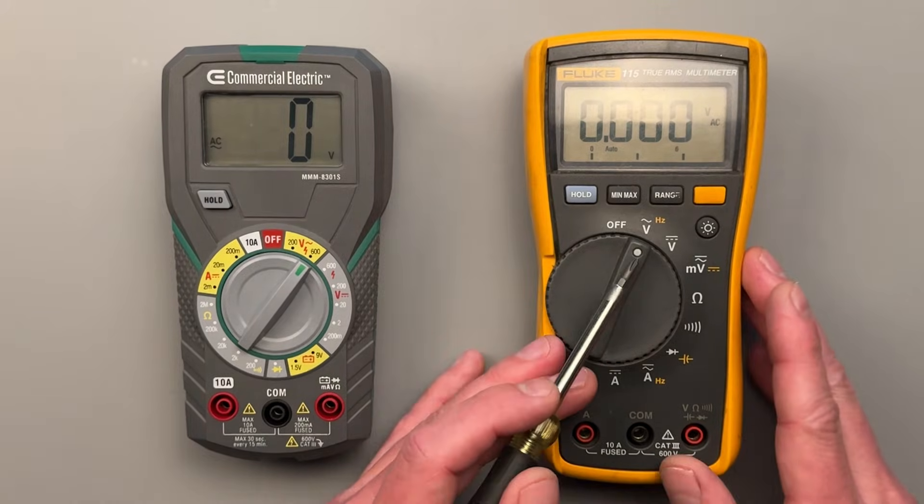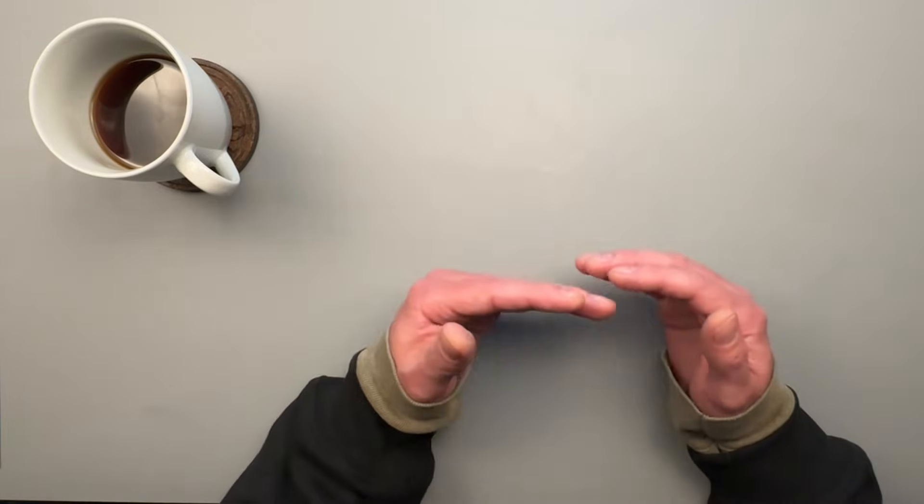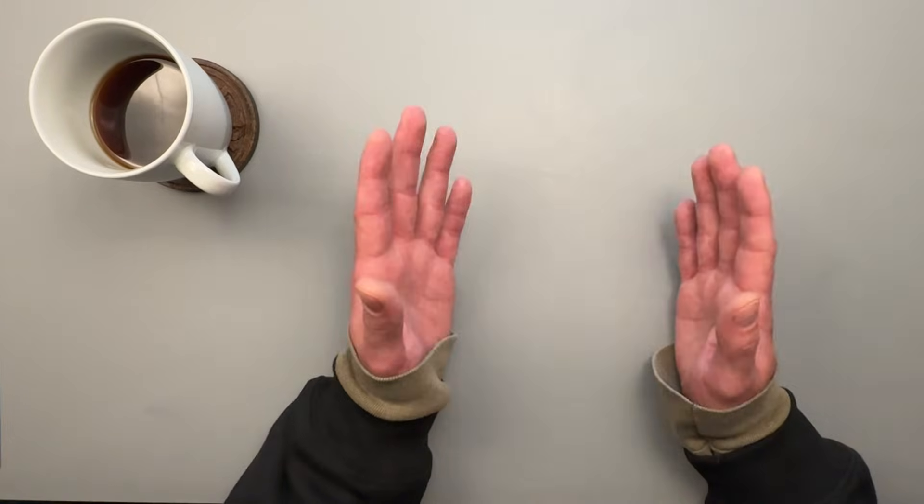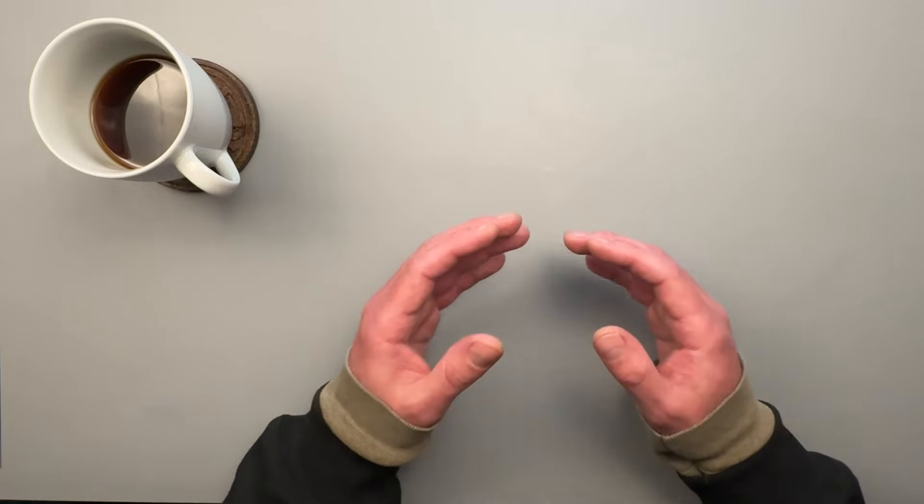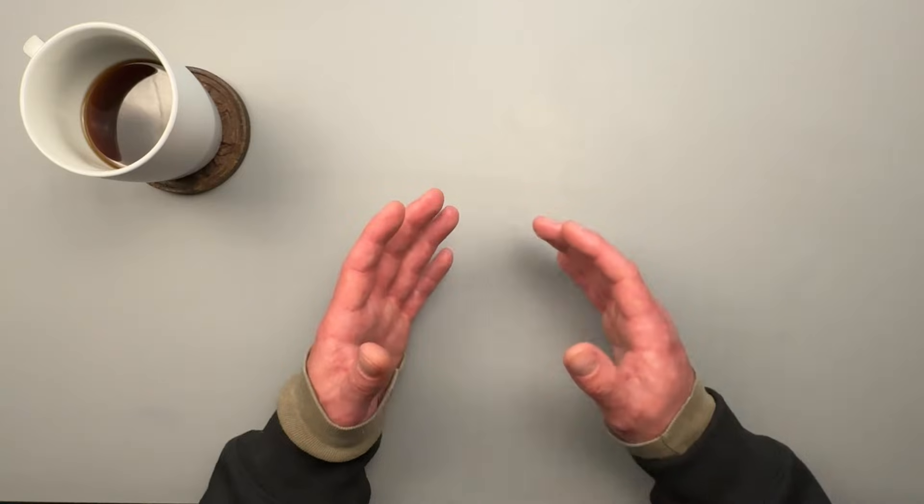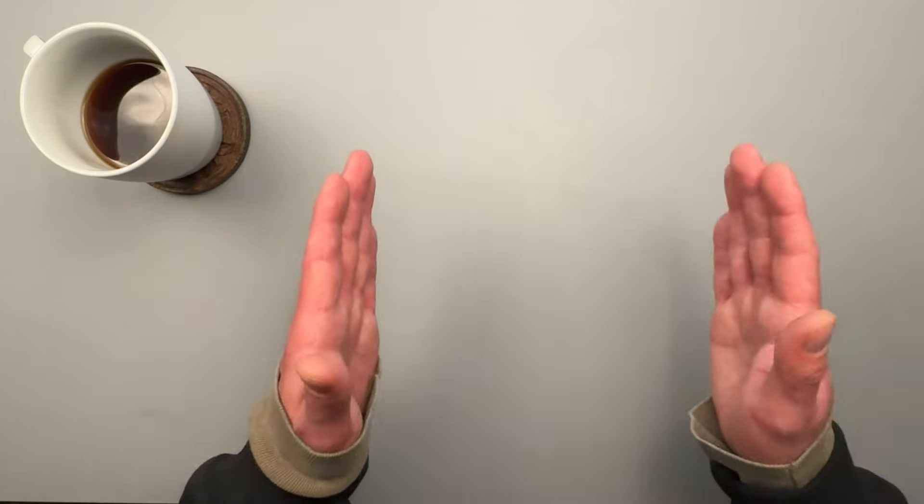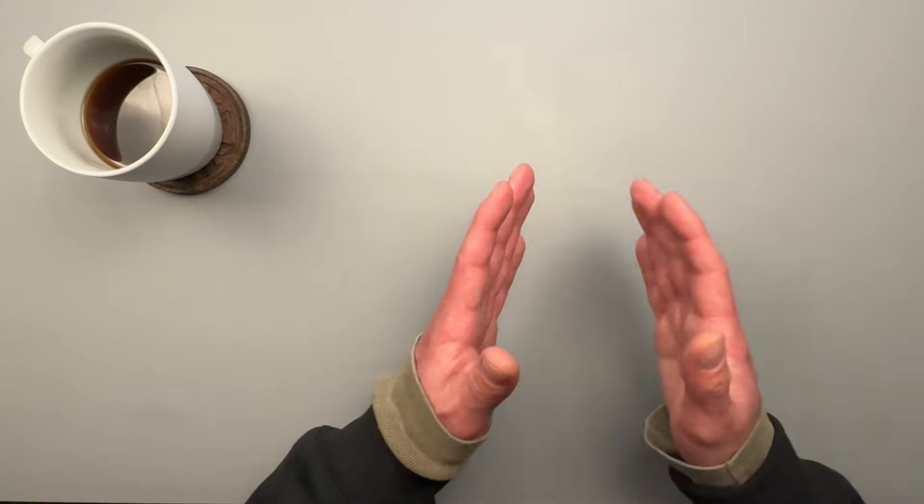An auto-ranging meter like we see on the right is able to detect and adjust its readings automatically without you having to change any settings. This range selection will also apply to our voltage DC, resistance, and current measurements. On a manually selecting meter, you must already have an idea of the range of voltage, current, and resistance when making a measurement.